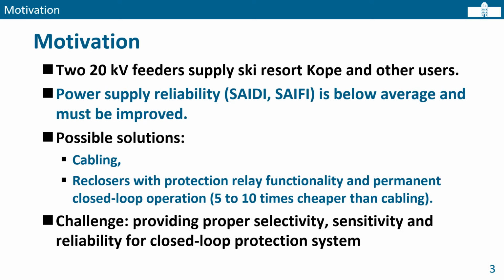Motivation for this work was the power supply reliability analysis in the grid of Elektro Celje, where it came out that two feeders are below the average values regarding SAIDI and SAIFI indices, and that some action is required to improve the situation. Possible solutions were cabling, which was pretty costly, and the second solution was the introduction of reclosers with protection relay functionality and permanent closed-loop operation, which was 5 to 10 times cheaper than cabling.